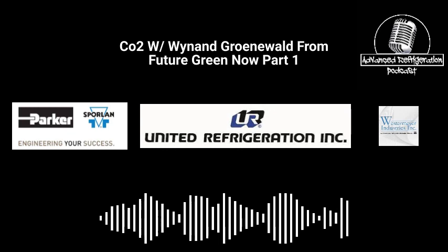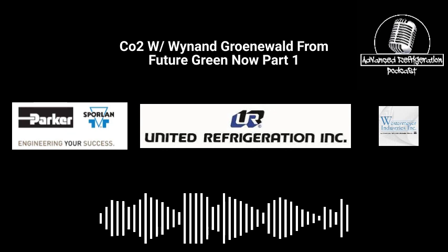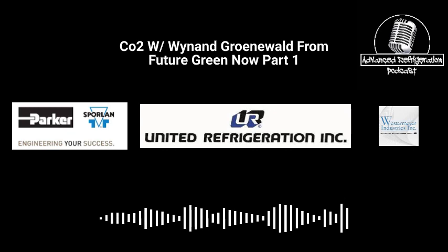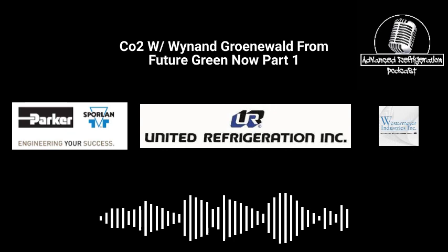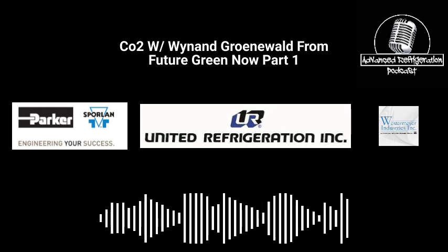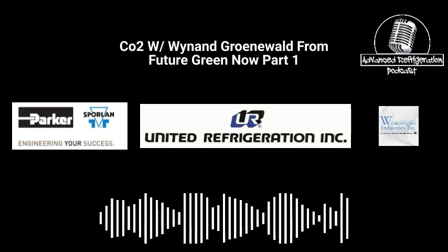I know most of the controllers don't have the ability to write to the set points like we need to. Is that something that could be advantageous, actually increasing the flash gas pressure to maybe 30, 40 pounds under the relief setting, just to load that thing up in the middle of the winter? Say it's 0 degrees outside, we need to juice the flash tank up to a higher pressure to keep the system running and keep the medium temp loaded up.